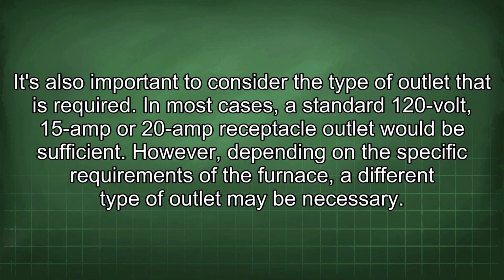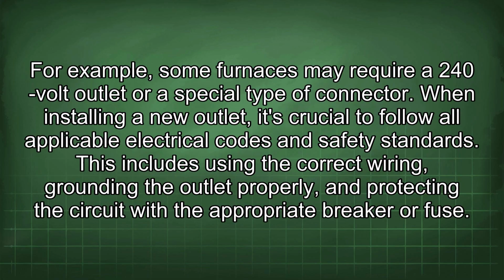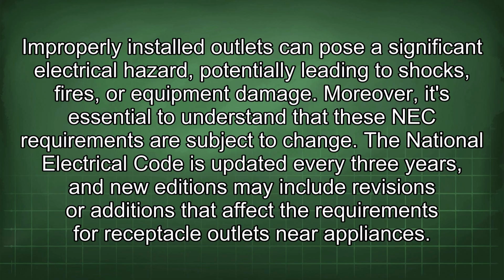It's also important to consider the type of outlet that is required. In most cases, a standard 120-volt, 15-amp or 20-amp receptacle outlet would be sufficient. However, depending on the specific requirements of the furnace, a different type of outlet may be necessary. For example, some furnaces may require a 240-volt outlet or a special type of connector. When installing a new outlet, it's crucial to follow all applicable electrical codes and safety standards. This includes using the correct wiring, grounding the outlet properly, and protecting the circuit with the appropriate breaker or fuse. Improperly installed outlets can pose a significant electrical hazard, potentially leading to shocks, fires, or equipment damage.